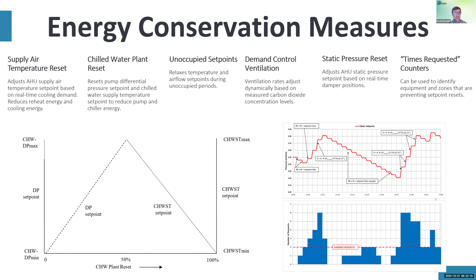We can also implement things such as schedules like occupied and unoccupied schedules, where during unoccupied times, we can relax temperature and airflow set points in order to save energy. We can implement things such as demand control ventilation, where ventilation rates can be dynamically adjusted to control measured carbon dioxide levels in the spaces. We can do other things such as use occupancy sensors to override, even during occupied times, temperature set points and airflow set points based on whether or not we're determining that the zone is populated or not. You could really go on and on. The number of energy conservation measures that you can implement is really just restricted by your own imagination.